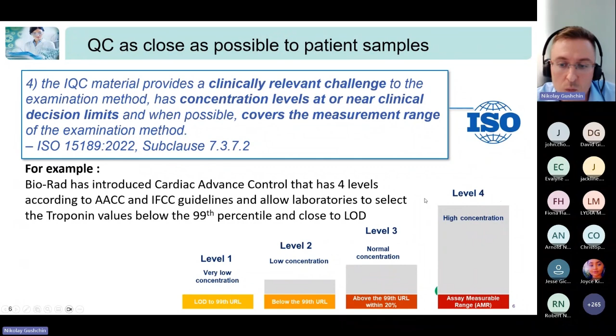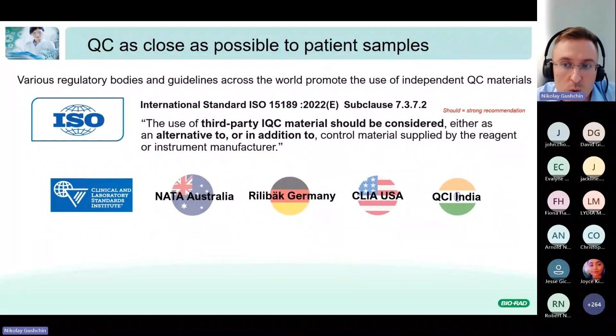Another important thing that ISO tells us is that we need to consider a third-party QC, either as an alternative to or in addition to the quality control material supplied by the reagent manufacturer. This is not only ISO. There are a lot of other standards, national guidelines of different countries or international ones, like CLSI, also having similar requirements about the use of third-party QC materials. It makes sense because independent QCs are produced independently from the reagent and from the instrument, and this is why they can give you the best estimation of how your test system performs.